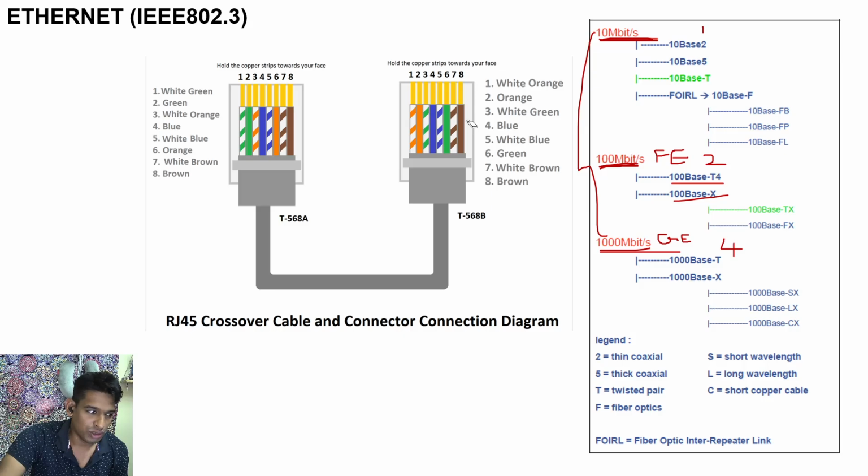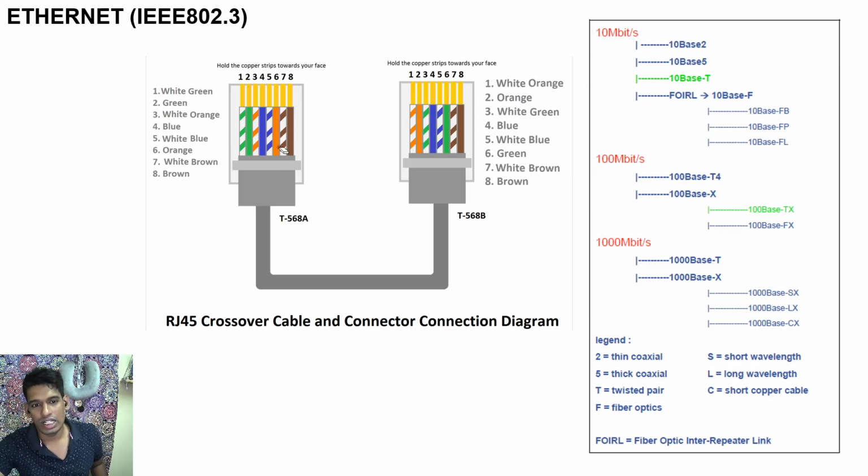But older computers do not, the NIC cards need not do so. All network interface cards in your computer might not do that, but all modern manufacturers generally keep that. Legacy laptops which are running Windows XP and so on might not recognize a new relay unless you use a crossover cable. If you are connecting directly to the relay, you need a crossover cable. All Ethernet switches support both crossover cables and straight through cables. So that is one more thing that you have to take care of when you're wiring Ethernet.